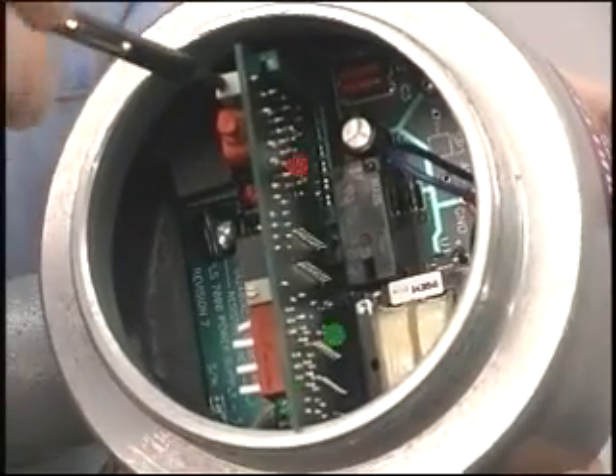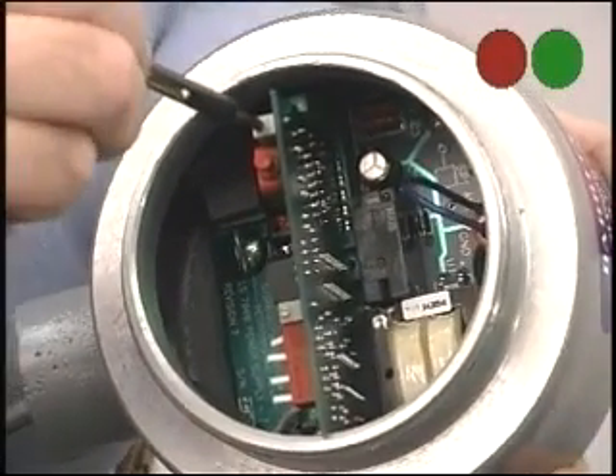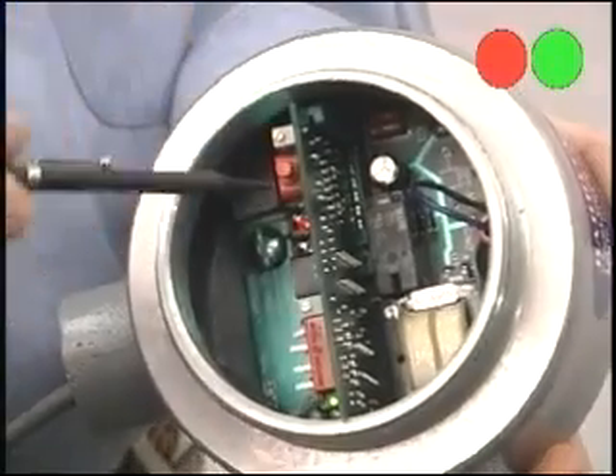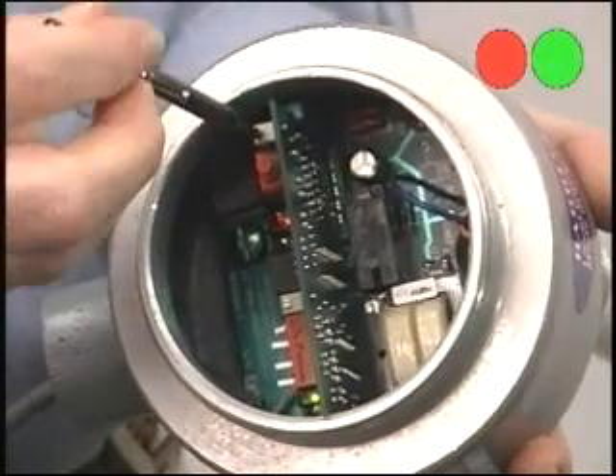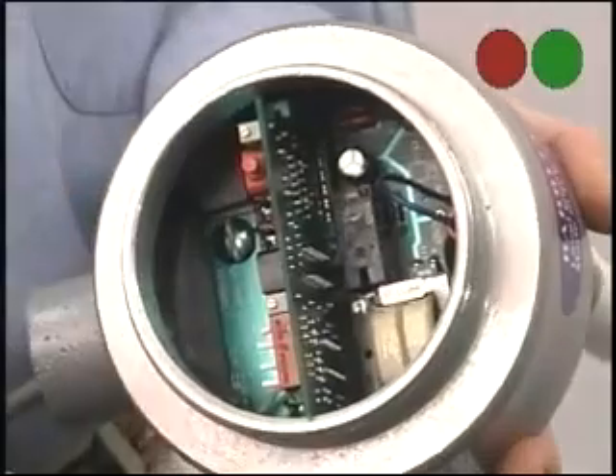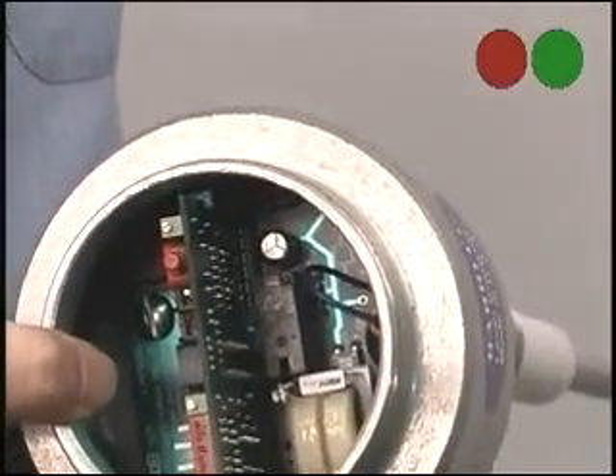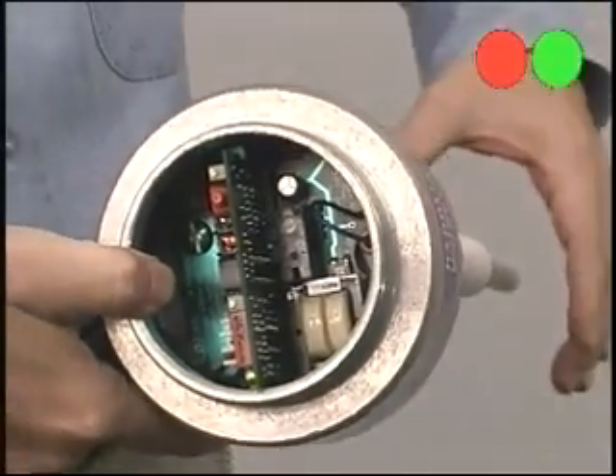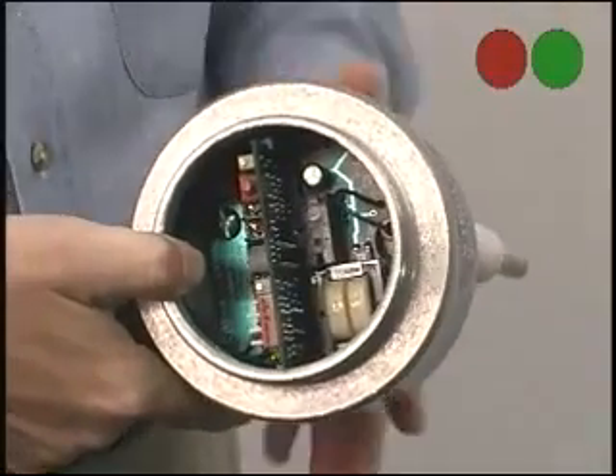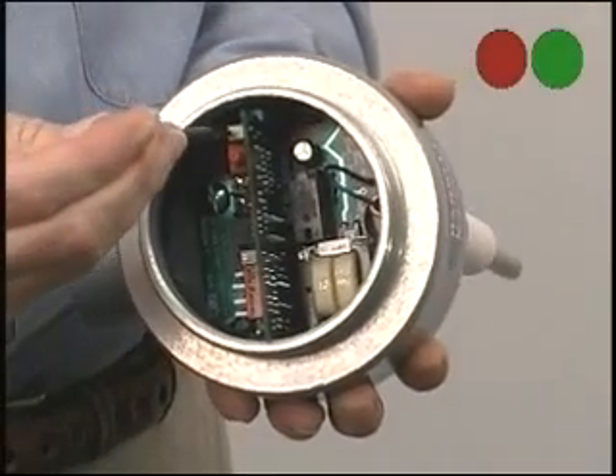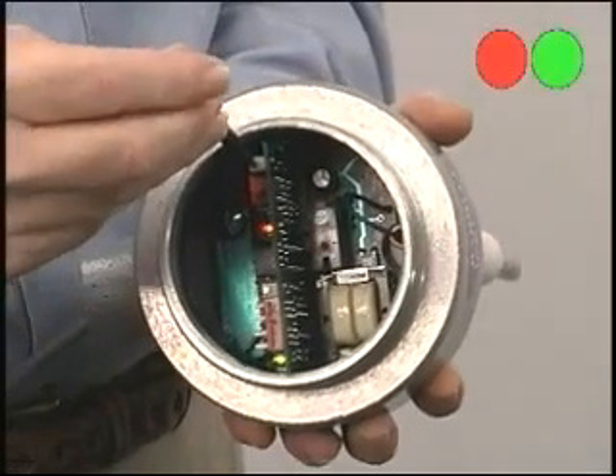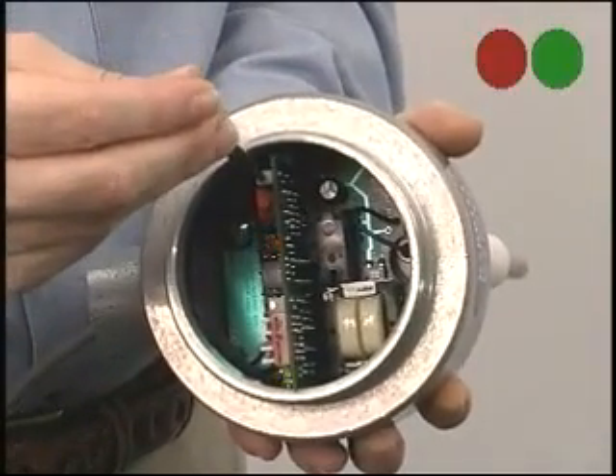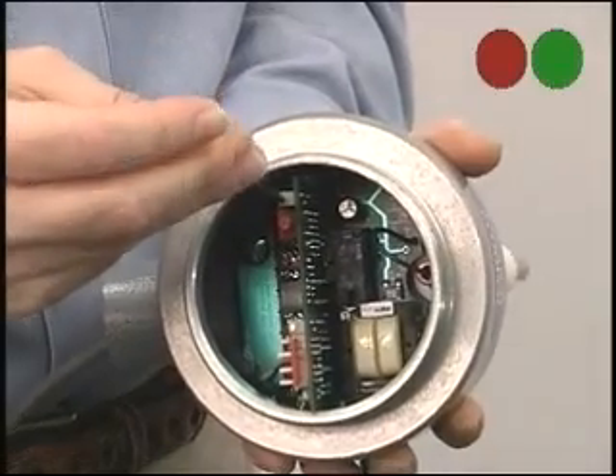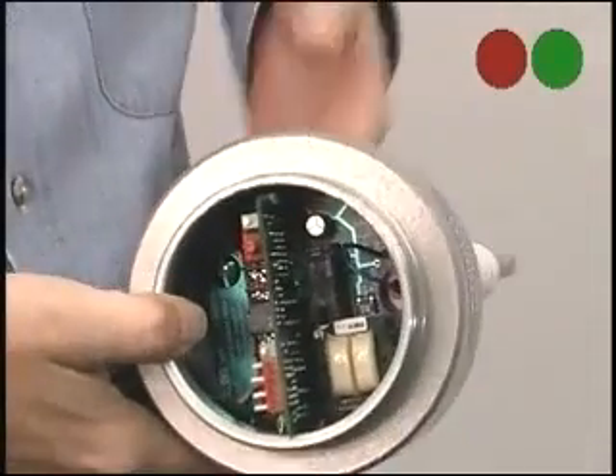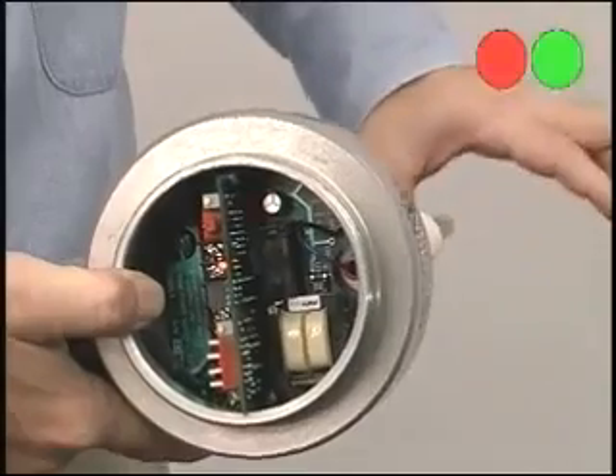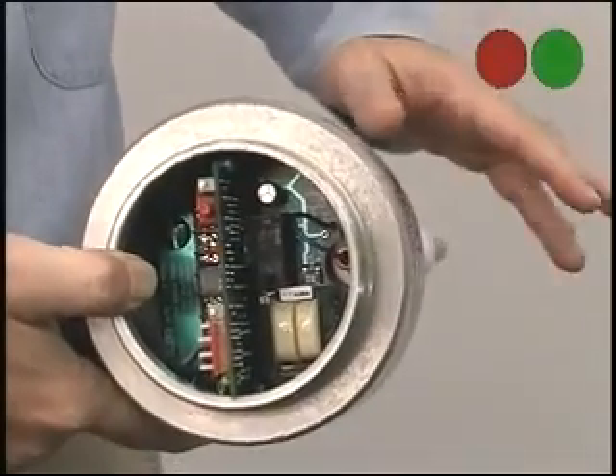To calibrate this unit is just as simple as falling off a log. Just turn the sensitivity adjustment clockwise until you fire the red LED, then you go counterclockwise until it just goes off. That's the maximum sensitivity of the unit. At that point, I don't even have to touch it to set it off. If that's too sensitive for your application, and it may be for most, I'll turn this clockwise, counterclockwise until it just goes off, and then I'm going to give it about half a turn further counterclockwise. Now getting close, doesn't do anything. I have to actually touch the probe to set it off.